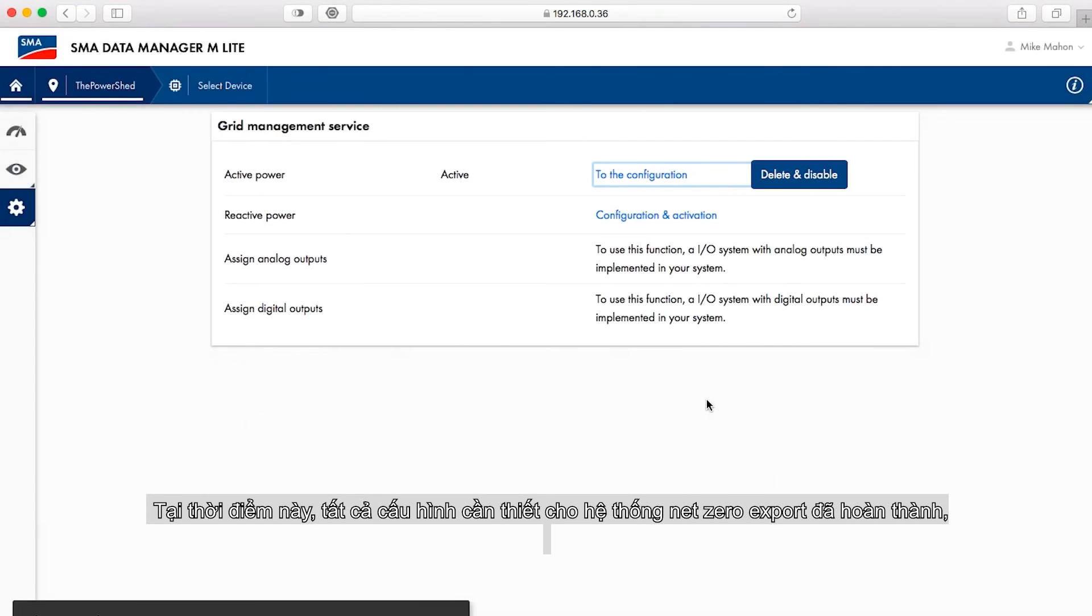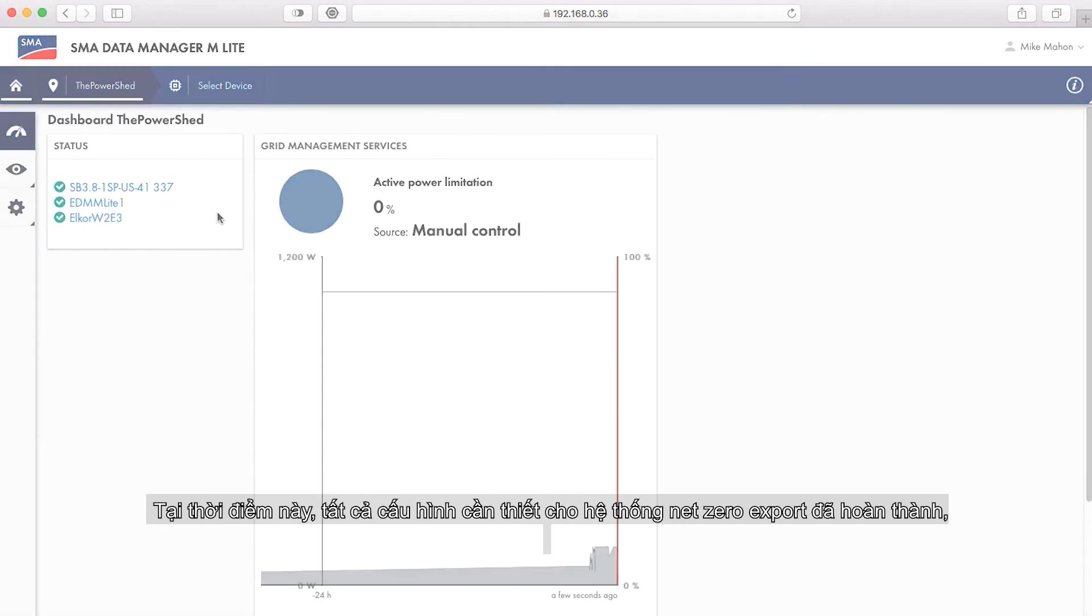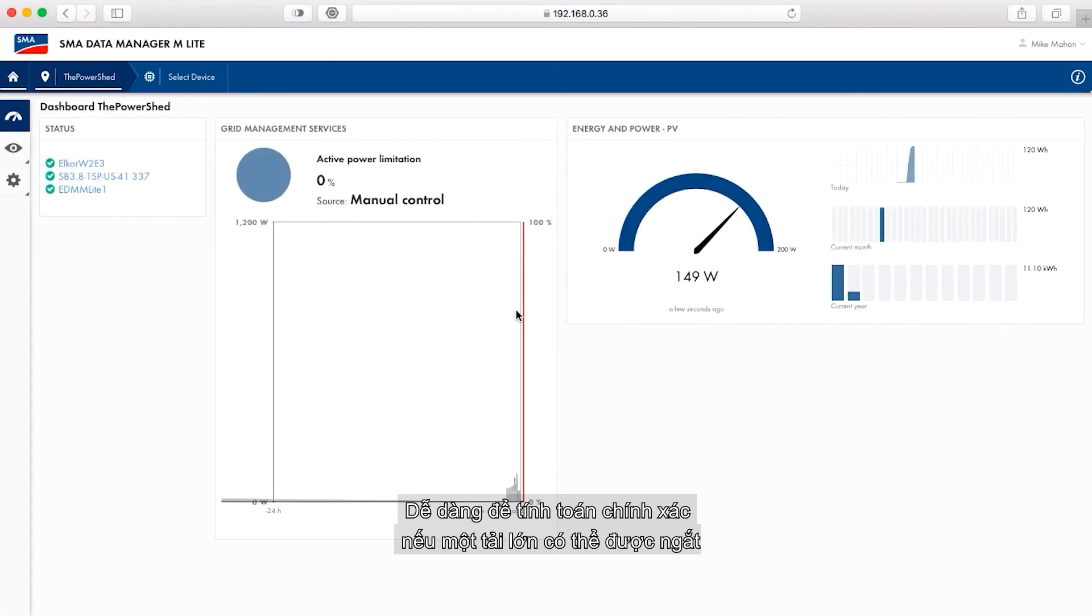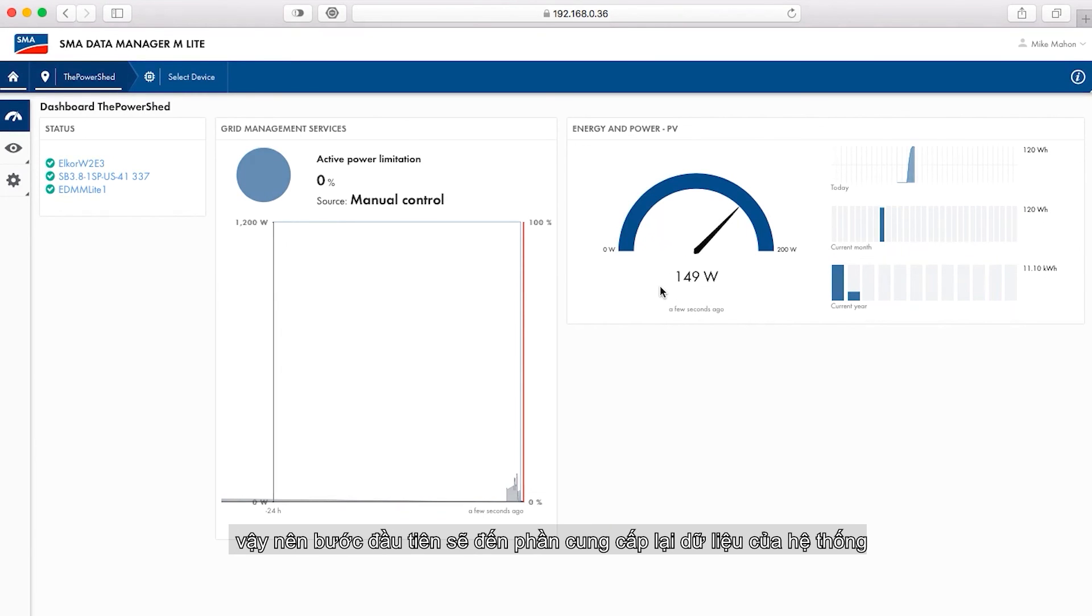At this point, all needed configuration for net zero export has been done. It is easiest to verify the correct operation if a large load can be shut off so that the system begins to backfeed.